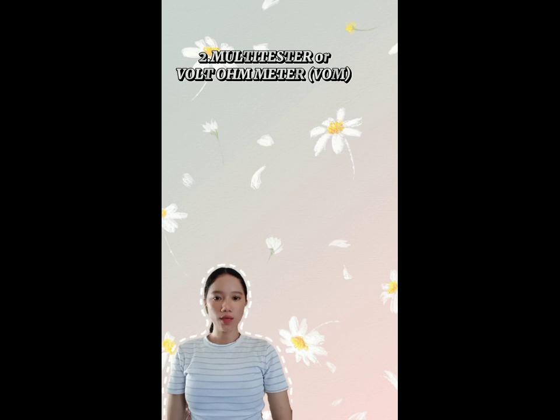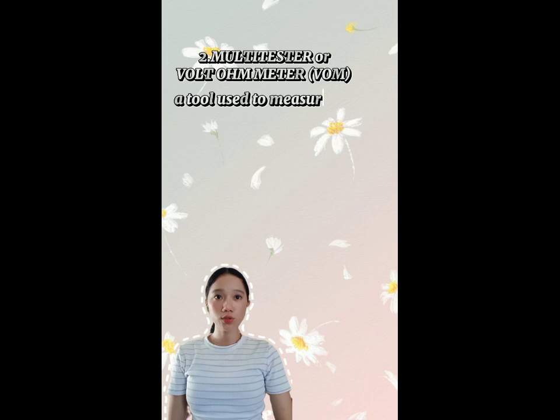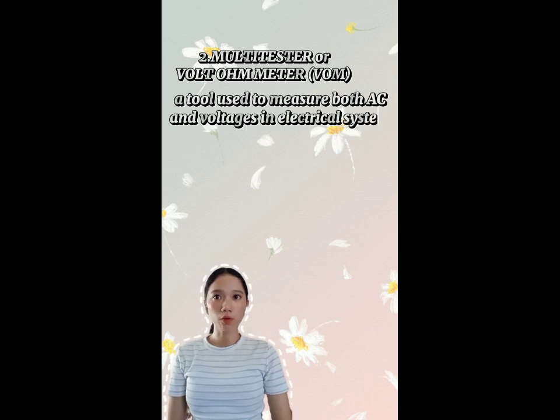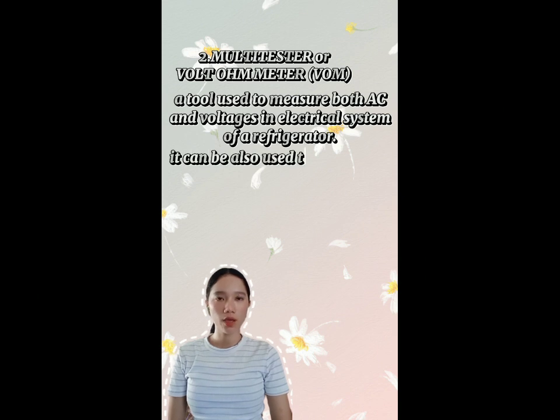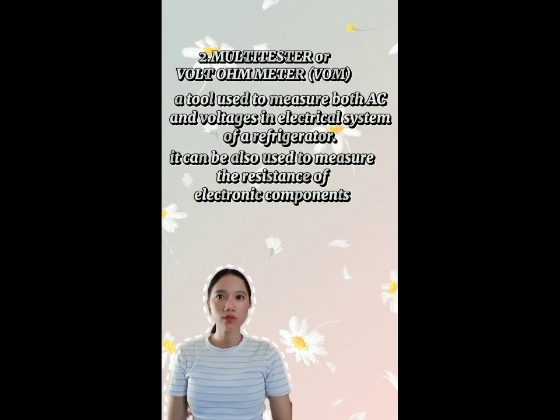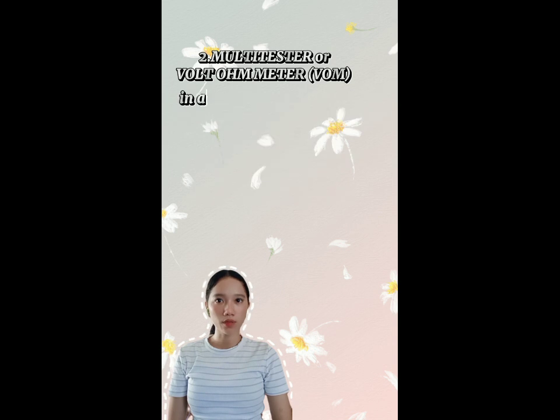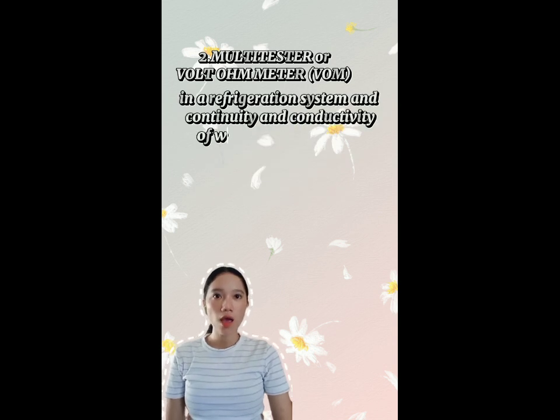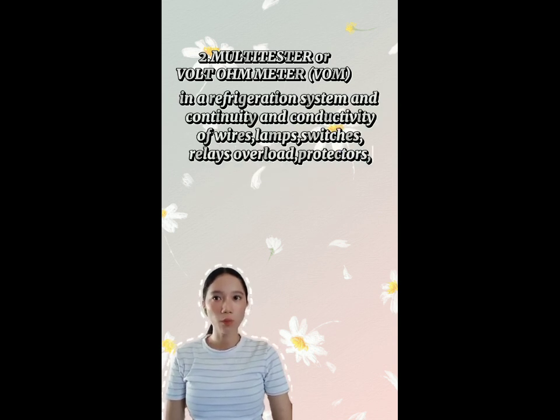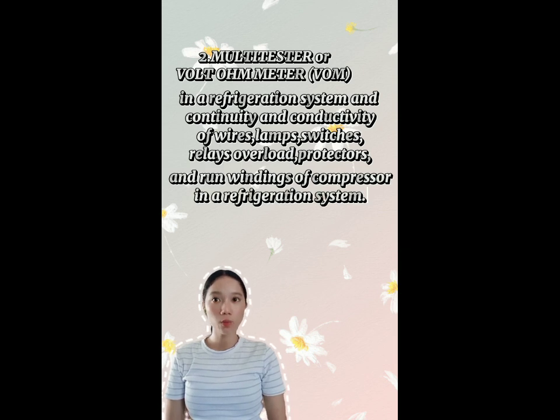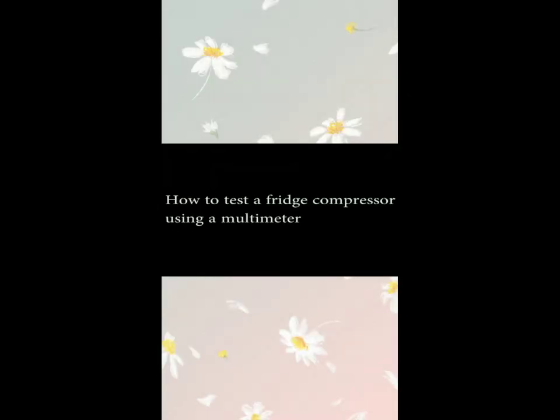Number 2 is a multi-tester or volt-ohm meter, a tool used to measure both AC and voltage in the electrical system of a refrigerator. It can also be used to measure the resistance of electronic components in a refrigeration system, and the continuity and conductivity of wires, lamps, switches, relays, overload protectors, and run windings of the compressor in a refrigeration system.